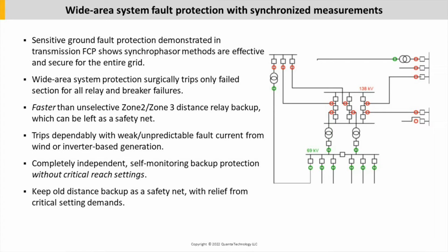In turn, this fault protection experience points to the use of a wide area platform for a new backup fault protection system that can accurately remove faulted power system sections not cleared by failed primary relays or circuit breakers, in less time than today's remote backup relays, without the critical settings coordination, and with any mix of inverter-based generation.